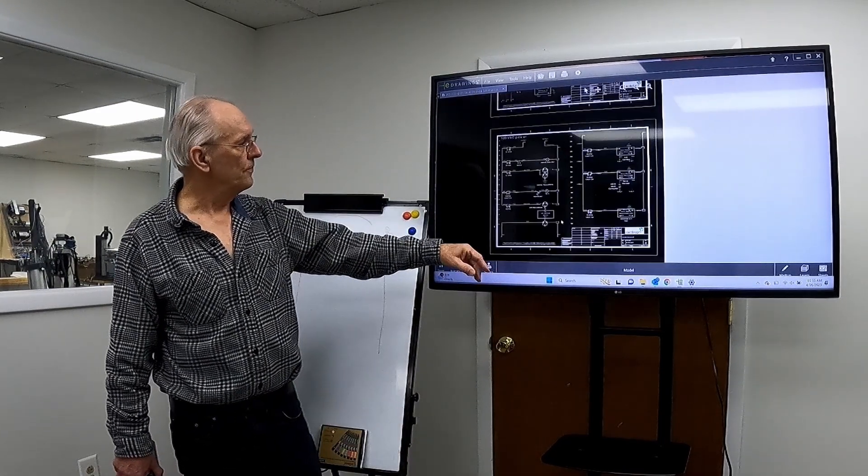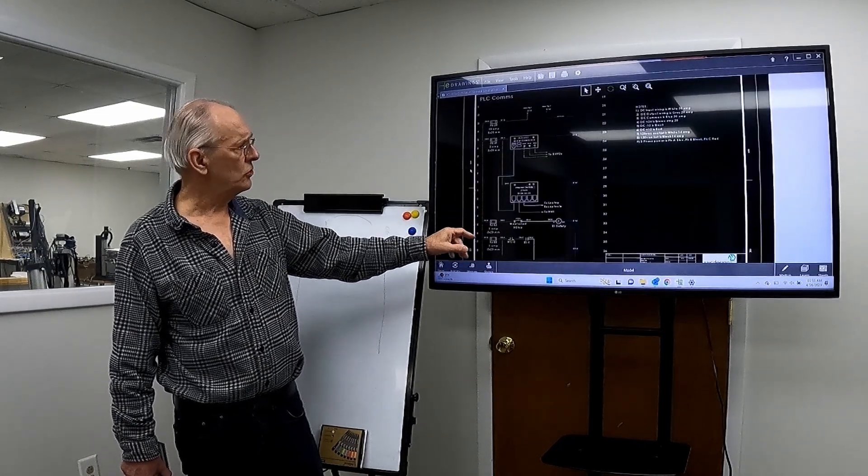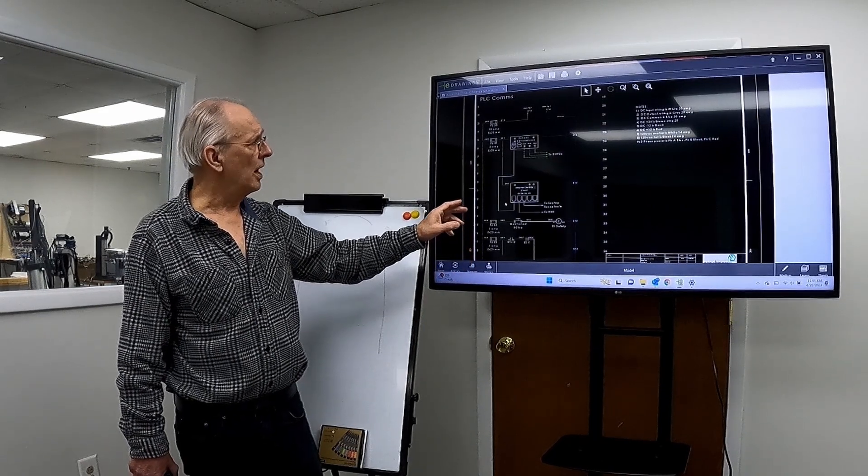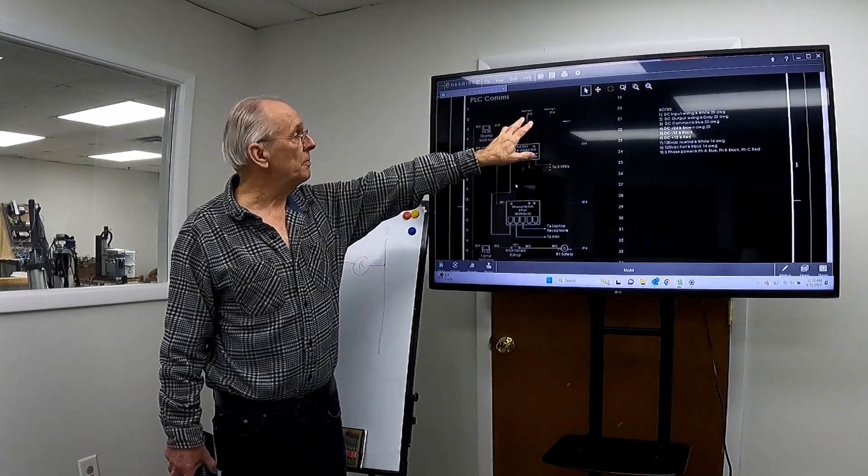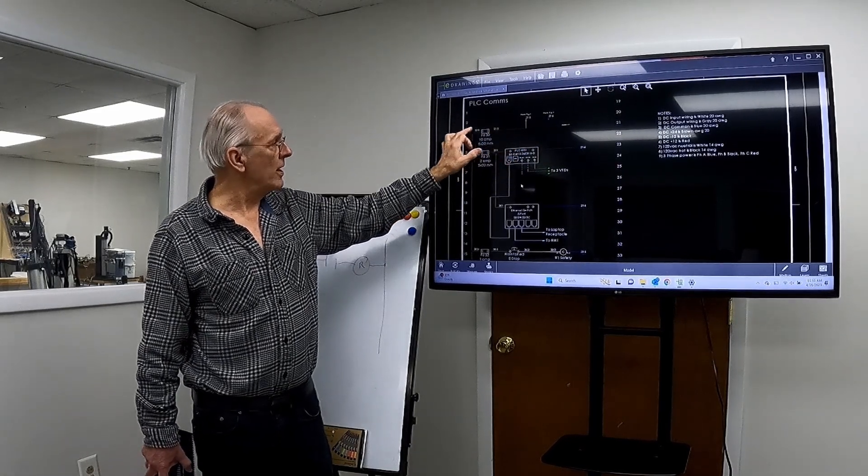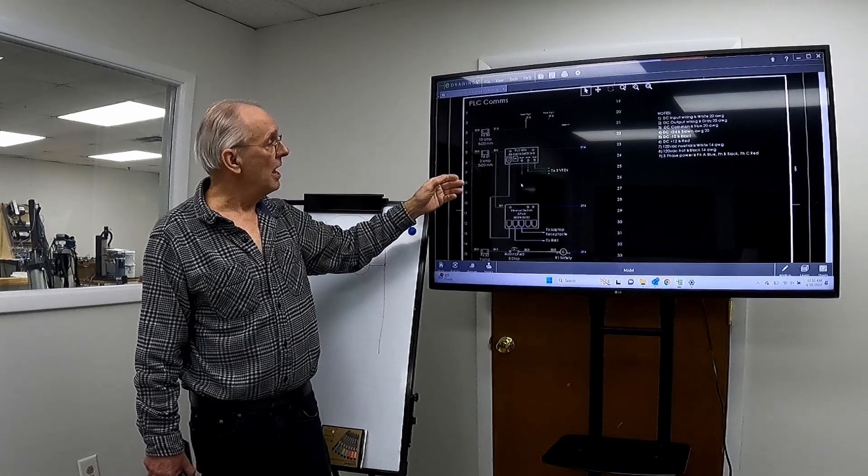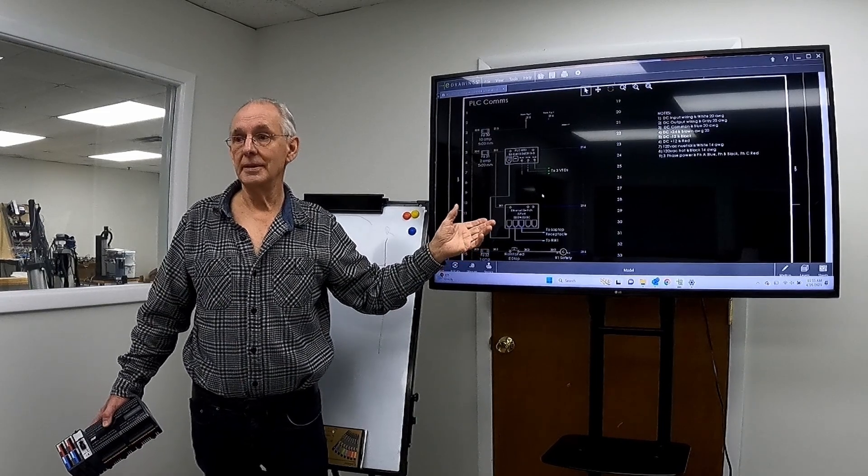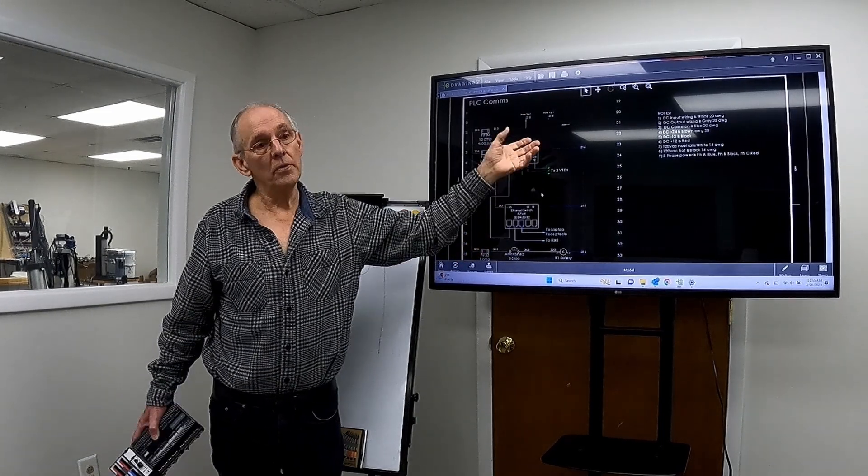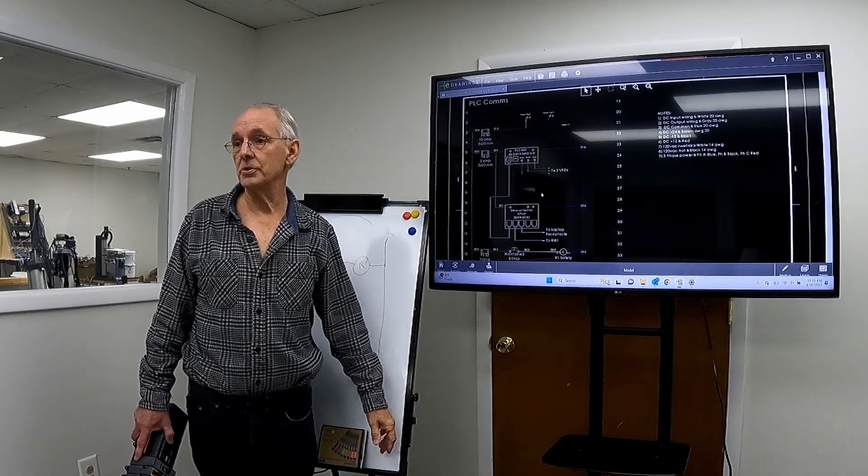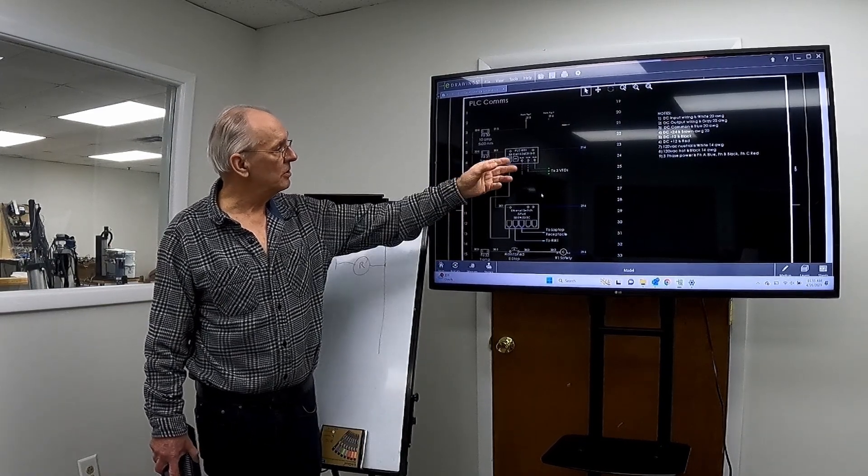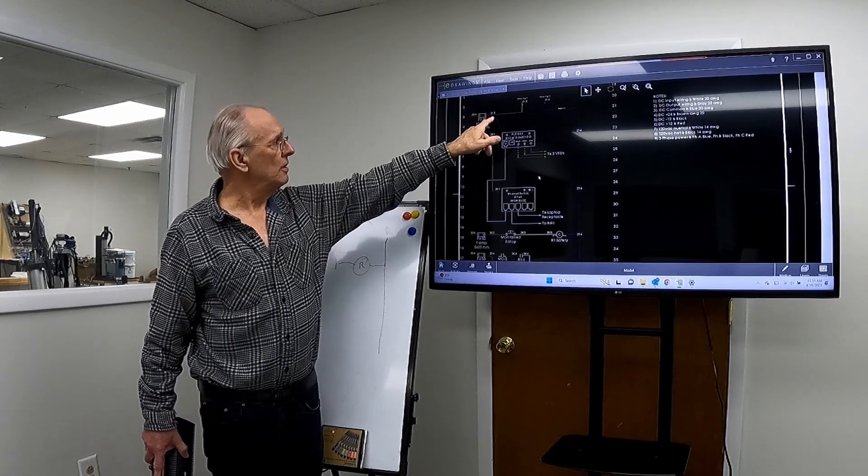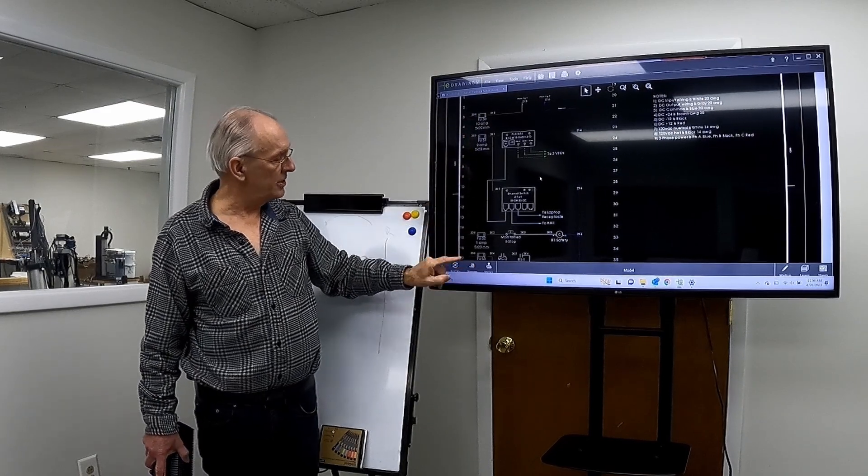Okay. So let's go down further, and here we're showing - this page just shows the power to the PLC. Now this is after the previous page. You can see it comes from, and then you'll notice that it comes to the fuse here, and the wire number changes to 300. And so everything on this page that originates on this page is a 300 number. And the 200 up here tells you, oh, that's actually coming from page two, so it's easy to keep track of where stuff comes from. And so this is just showing the power to the PLC, which is on all the time, and you notice there's a fuse, a single fuse at the top, and then more fuses down below.